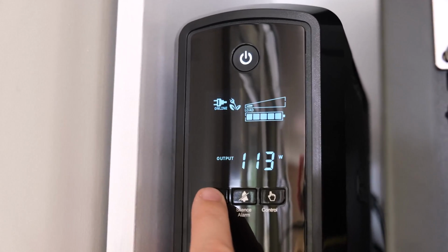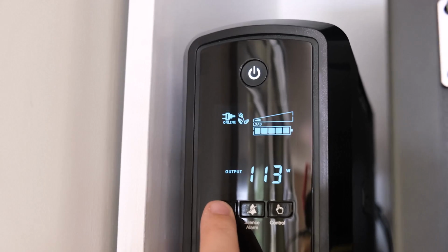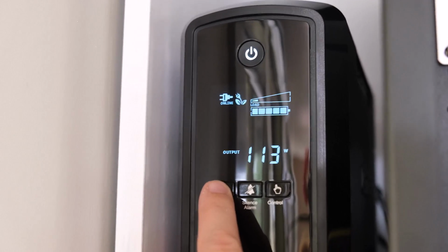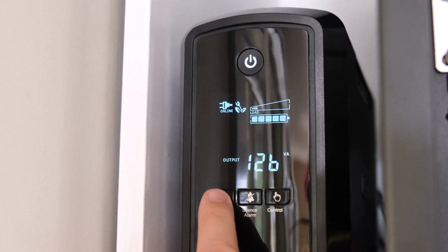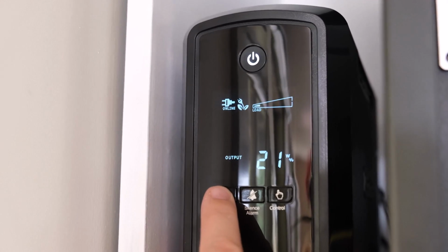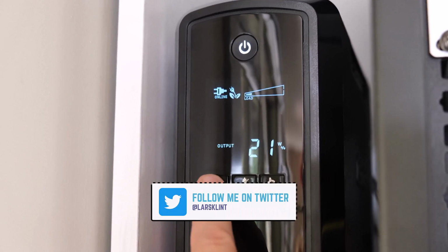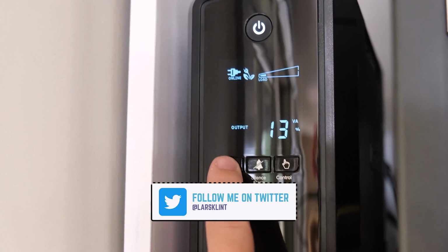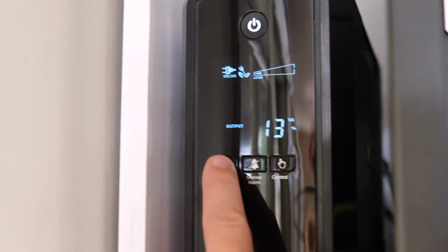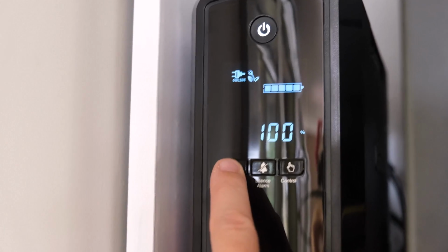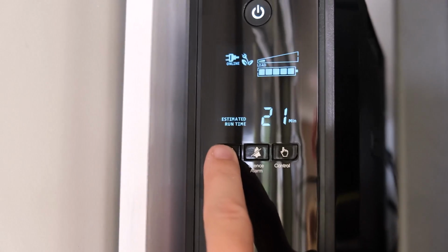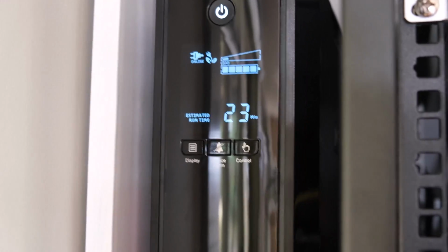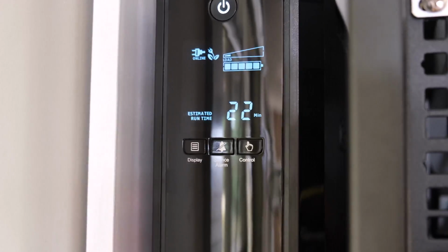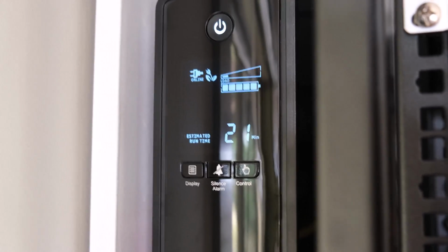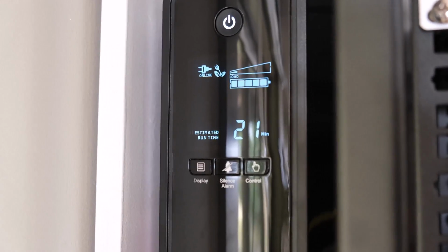50 hertz. 500 hertz, that'd be interesting. And 113 watt output. Okay. 126 VA. Still don't know what this volt percentage is, but anyway. Maybe it's of the entire volt budget. Could be. 100%. And 23 minutes we get, 21 minutes. Let's see when everything is powered up. It might be different, but 20 minutes, I can live with that. I have enough time to shut things off properly, etc., if I need to.